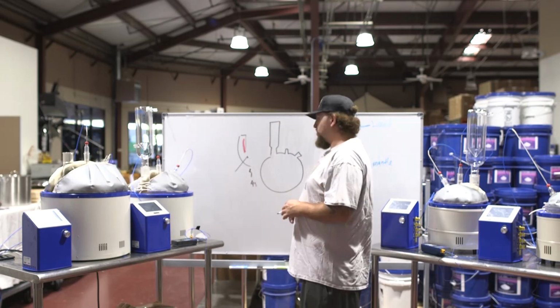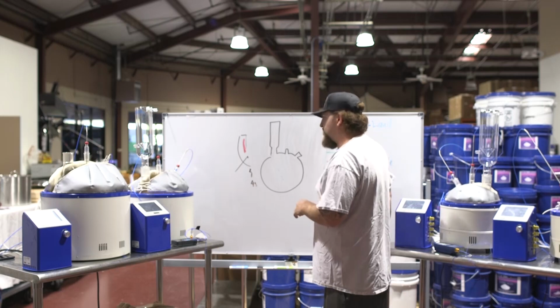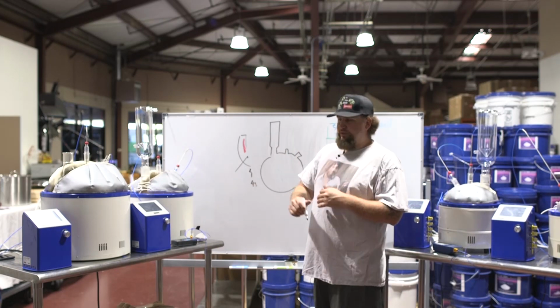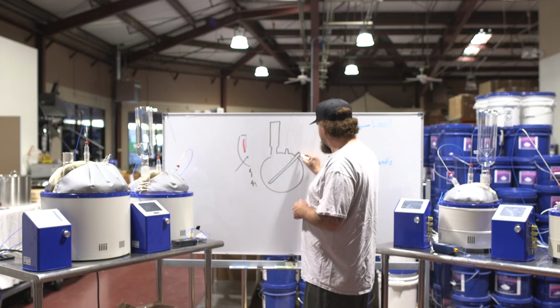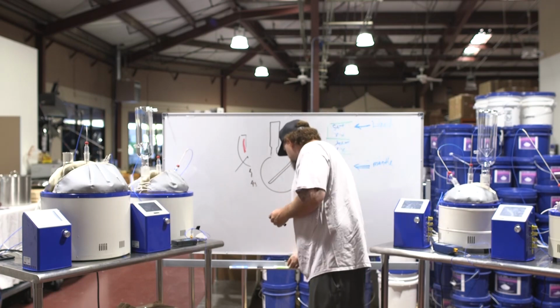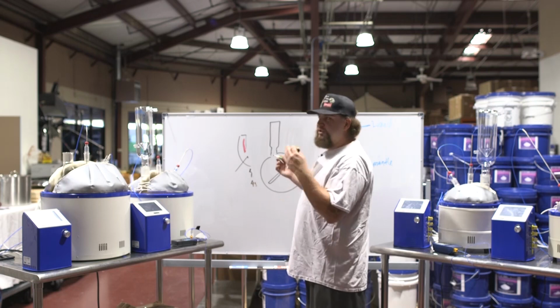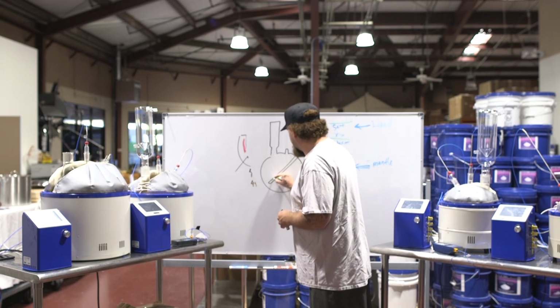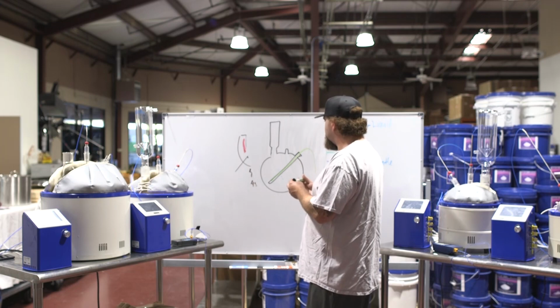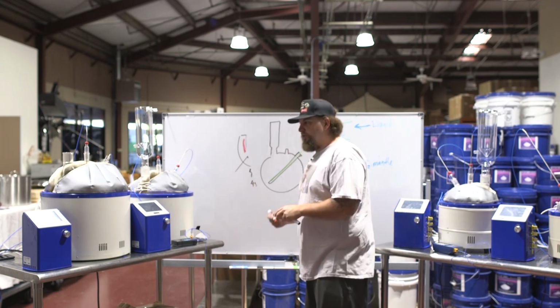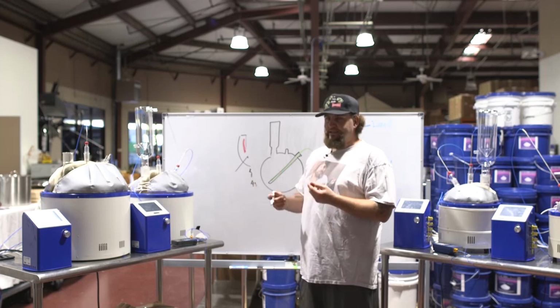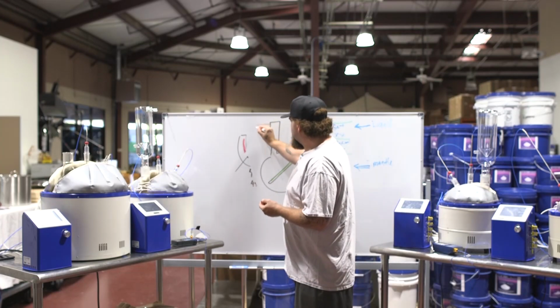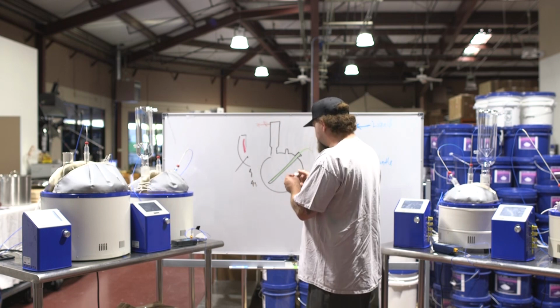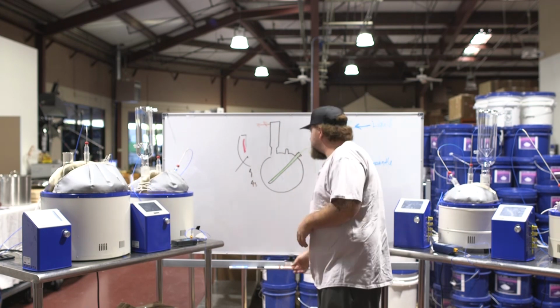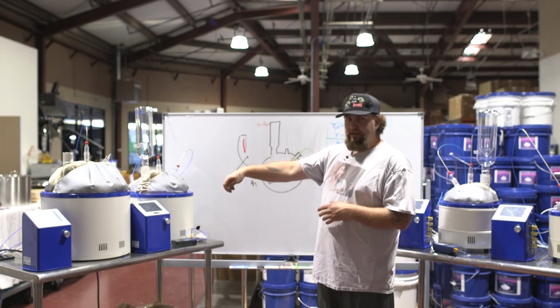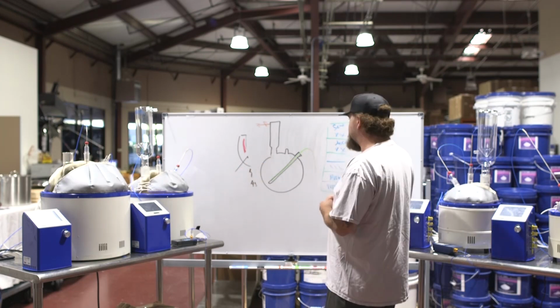So this will be an example with the well, and the reason the well is different is because the well will always be a couple degrees different than putting the liquid in there. So let's say you have a well in here. And now we put the probe. You just need one at first. You really don't need to do anything else. You could use more, but you're only testing against a single standard, so you only need one probe. Okay, so essentially what we would do is install the mantle, put the liquid probe into the first port because we're going to read off the liquid probe.